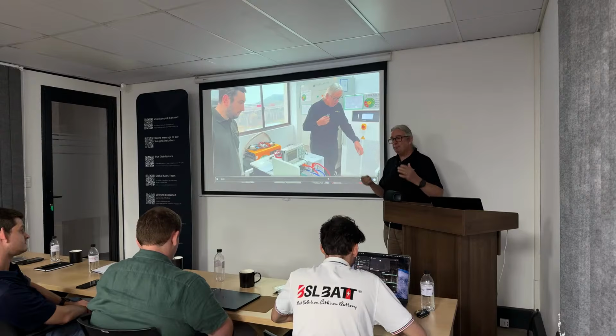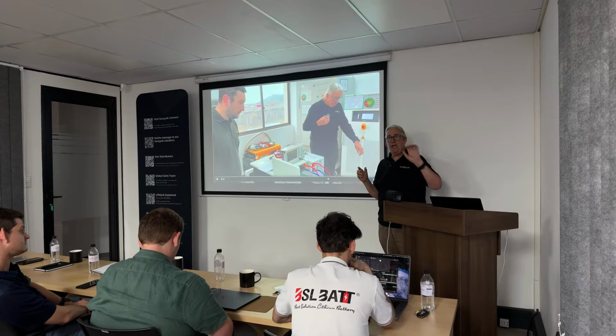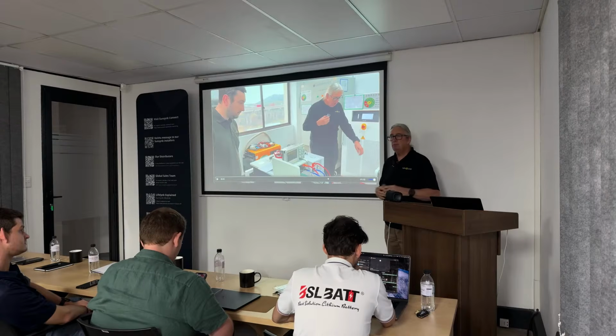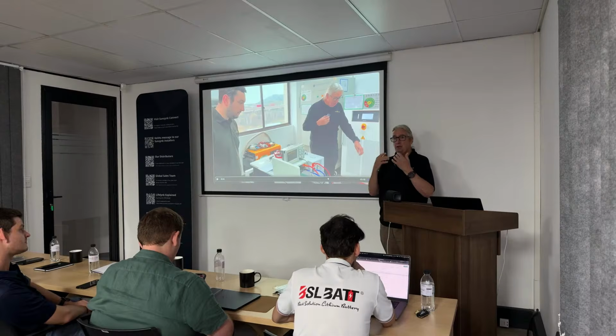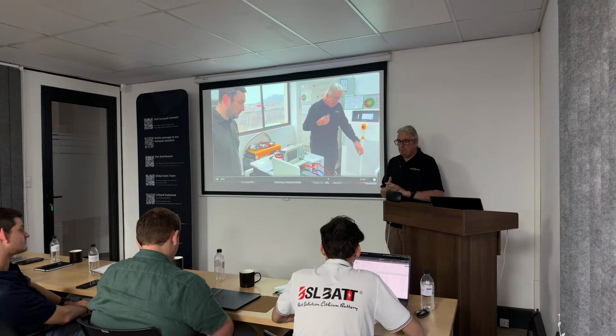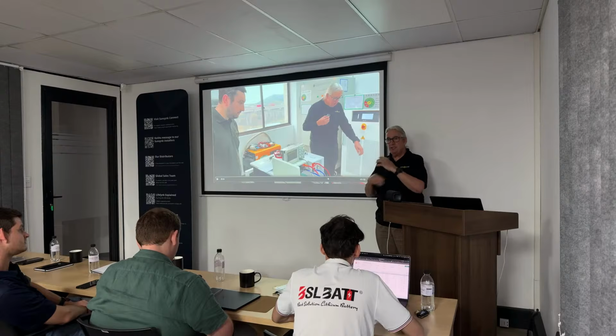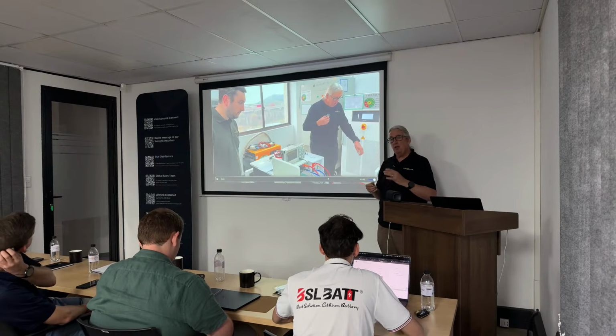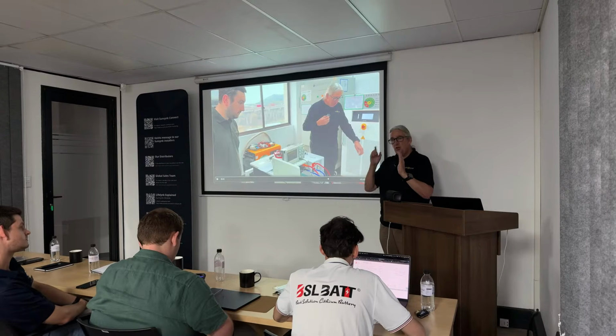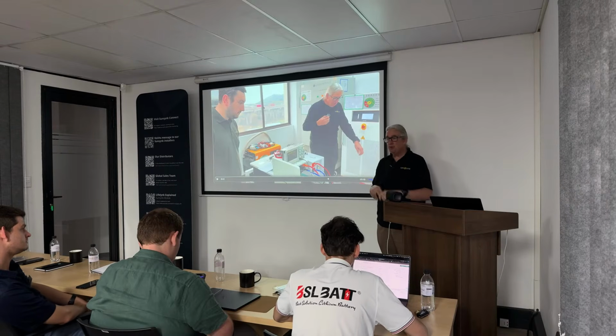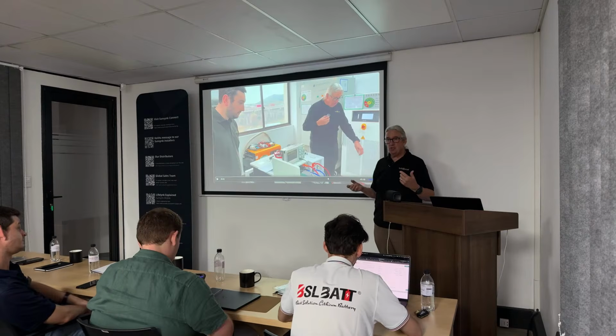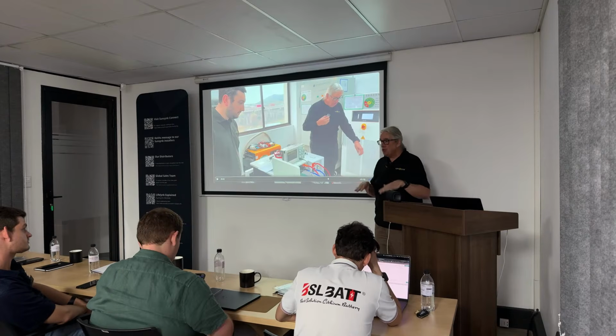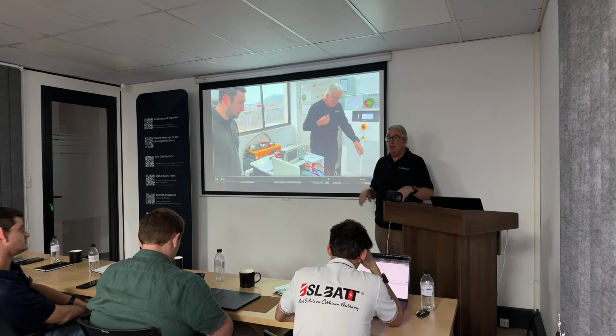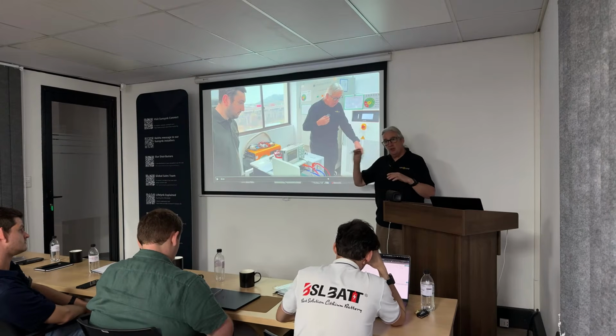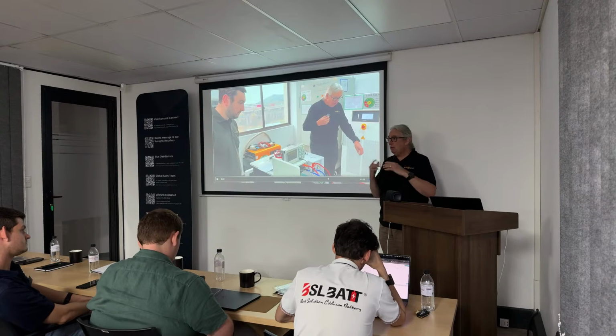But if you have a power cut, and the inverter is, say for argument's sake, 8 kilowatts, and you're drawing 12 kilowatts of power, what's going to happen? The inverter's going to trip if you're taking the whole house through it. So the whole house being fed, the unit will trip. But then it will reset automatically and come back on again, but with just the essentials - the non-essential load will cut out. So it's got two outputs. If your load on the non-essential is lower than the rating of the inverter, it won't cut. If it's greater, it will cut the non-essential off, and then you can come back and press the button.